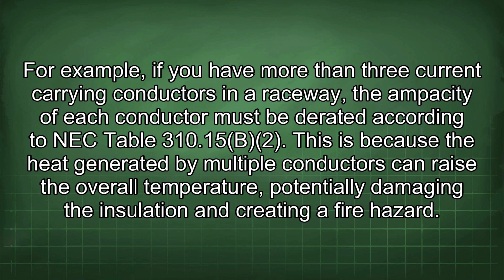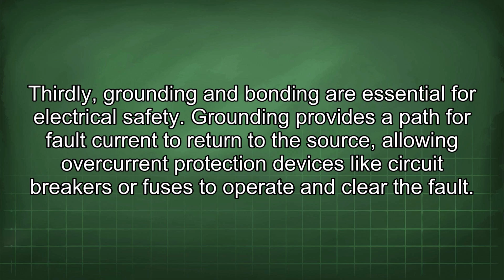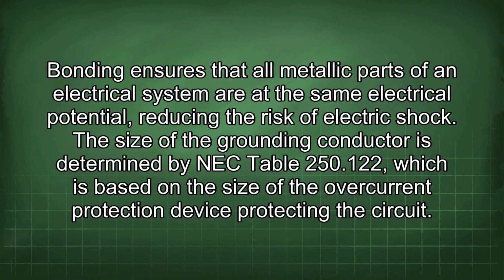For example, if you have more than 3 current-carrying conductors in a raceway, the ampacity of each conductor must be derated according to NEC Table 310.15(B)(2). This is because the heat generated by multiple conductors can raise the overall temperature, potentially damaging the insulation and creating a fire hazard. Thirdly, grounding and bonding are essential for electrical safety. Grounding provides a path for fault current to return to the source, allowing overcurrent protection devices like circuit breakers or fuses to operate and clear the fault. Bonding ensures that all metallic parts of an electrical system are at the same electrical potential, reducing the risk of electric shock. The size of the grounding conductor is determined by NEC Table 250.122, which is based on the size of the overcurrent protection device protecting the circuit.